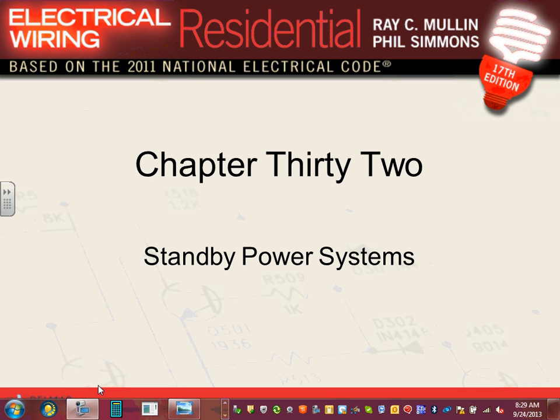Legally required: if you have a jail with a bunch of locks and a bunch of heating systems, these are also required to be backed up, because you cannot evacuate those people somewhere else if you lose power. You need to continue to operate. So they have a system, required by code, that comes up to speed, energizes, and feeds the building.